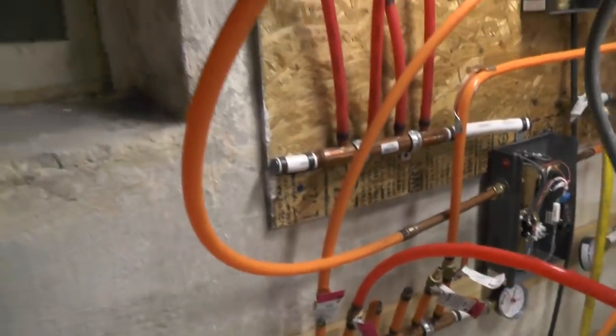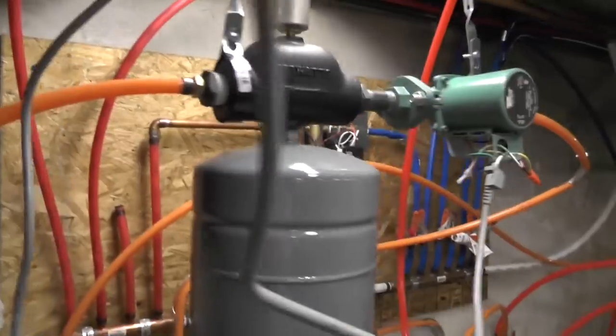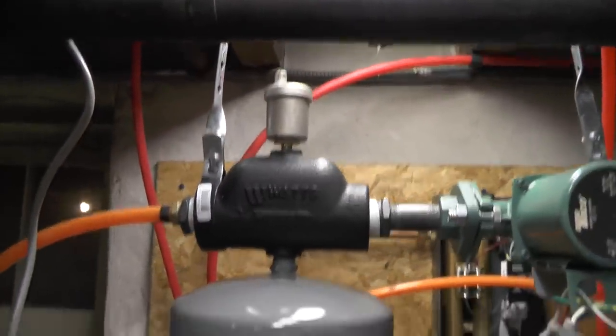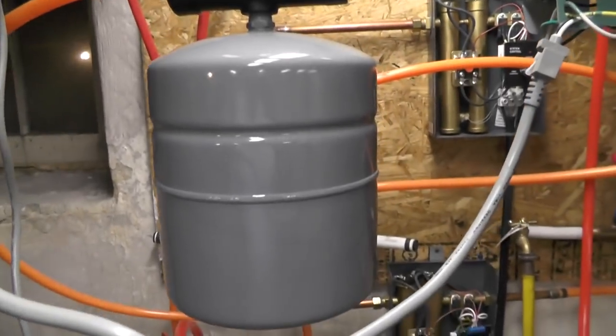So then when the hot water comes out of the heater that loops up here, comes into my air separator with the automatic air purge valve up top and a 15 psi pressure tank below.